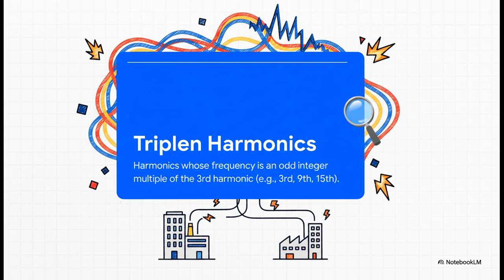Not all harmonics are created equal. There's a particular group that's especially nasty, especially in the three-phase power systems that run most of our commercial buildings. They're called triplens, that's the 3rd, 9th, 15th harmonic, and so on. These have a dangerous habit of ganging up where you'd least expect it.